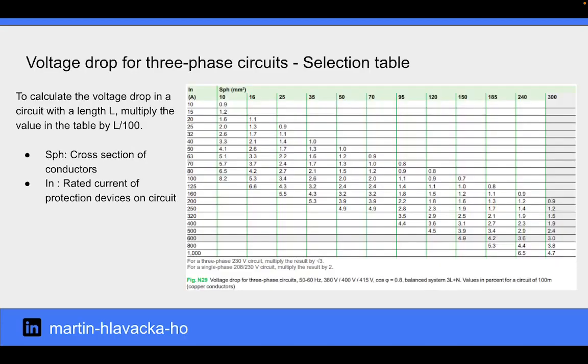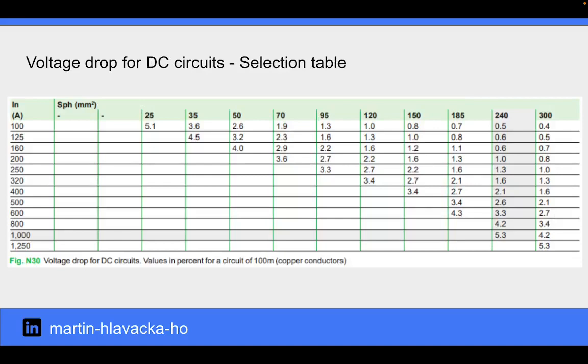This selection table indicates the voltage drop for three-phase circuits in percent for a circuit made up of 100 meters of cable. If the voltage drop exceeds 3%, increase the cross-section of conductors. This selection table indicates the voltage drop for DC circuits in percent for a circuit made up of 100 meters of cable. If the voltage drop exceeds 1%, increase the cross-section of conductors.